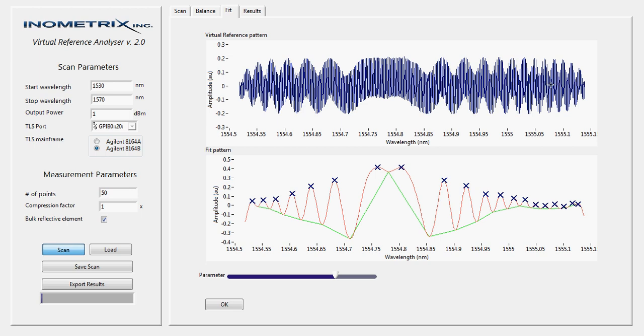So we're trying to extract the envelope of this interference pattern. We do that by using a fit. We fit to this interference pattern, and we extract the envelope. The envelope of this pattern, which is shown here, is equivalent to the first order interference pattern that would be produced in a traditional dual arm interferometer. Some examples would be the Michelson or the Mach-Zehnder interferometer. So it's exactly the same.